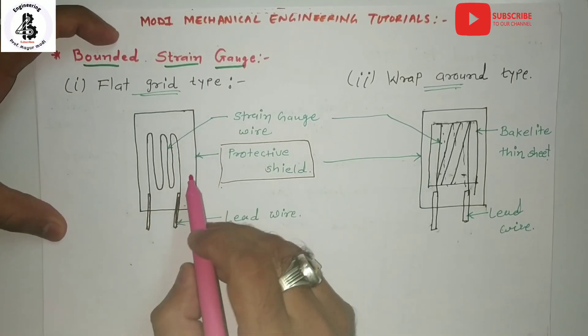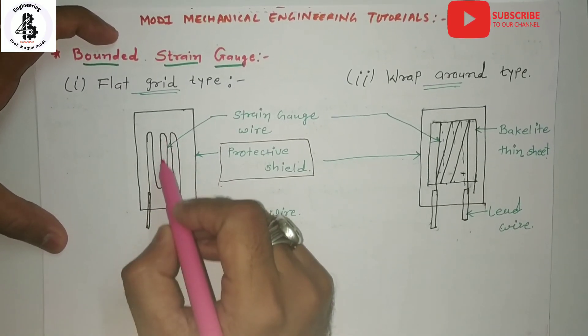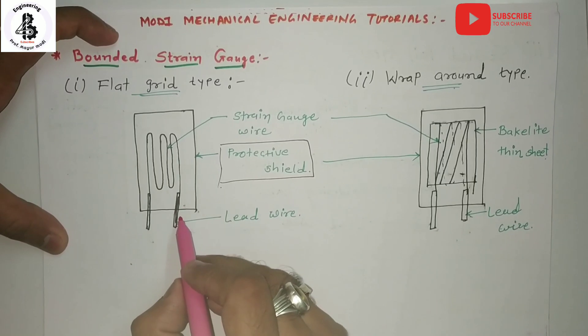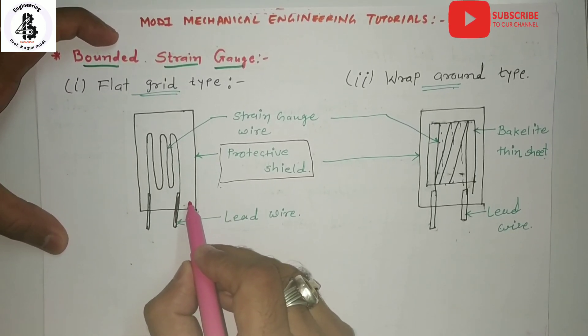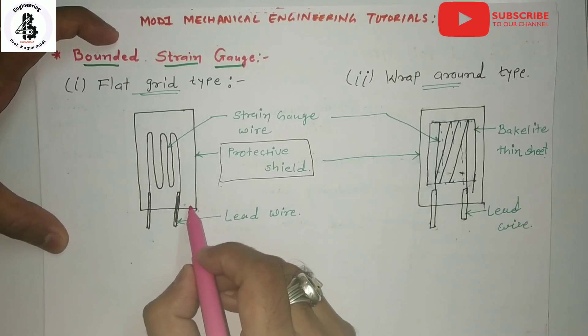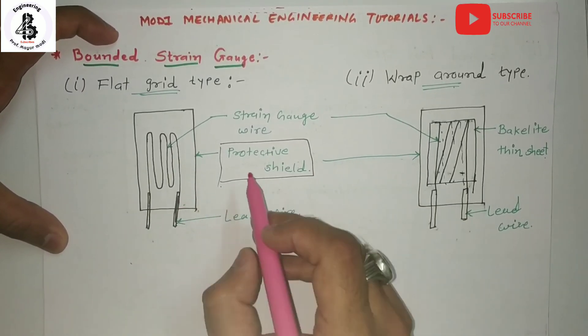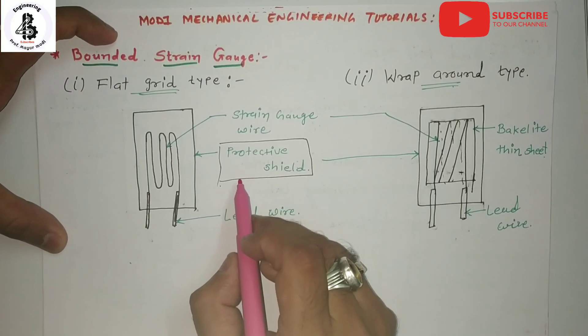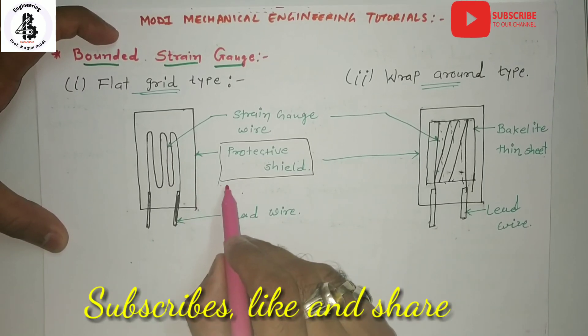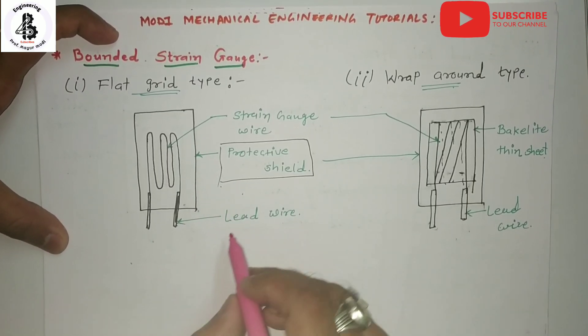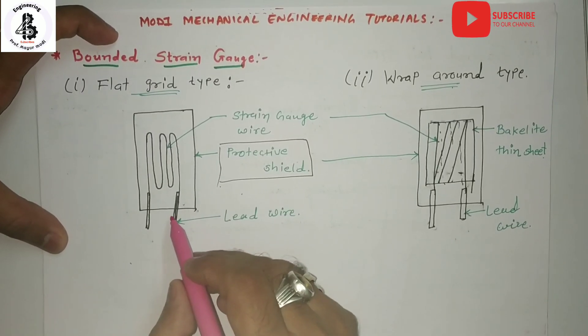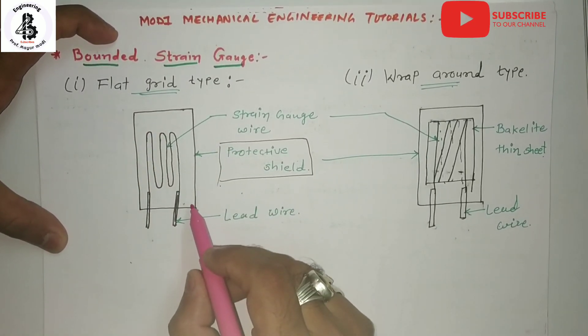In the flat grid type, the wire is wound back and forth as a grid, as seen in the figure. The grid structure is bonded to the backing material such as paper, epoxy bonding agent, or some adhesive, along with a protective cover. Since the ends of each section of the wire are looped around, the transverse strain also causes changes in resistance in that section of the wire. Lead wires are connected to the system to reflect the change in strain.